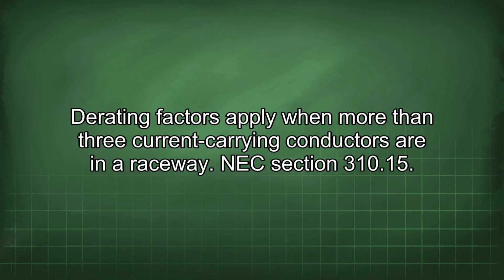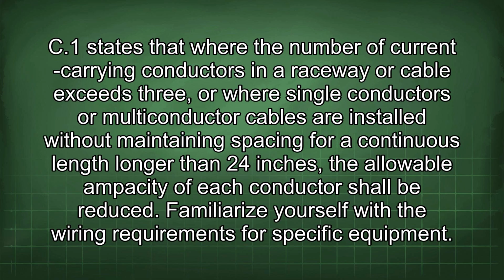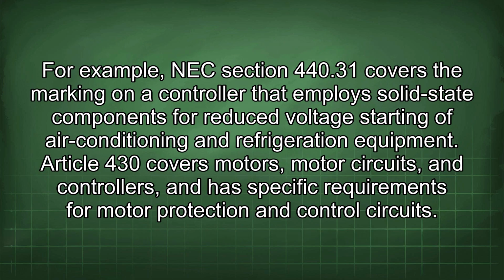NEC Section 310.15(C)(1) states that where the number of current carrying conductors in a raceway or cable exceeds 3, or where single conductors or multi-conductor cables are installed without maintaining spacing for a continuous length longer than 24 inches, the allowable ampacity of each conductor shall be reduced. Familiarize yourself with the wiring requirements for specific equipment.